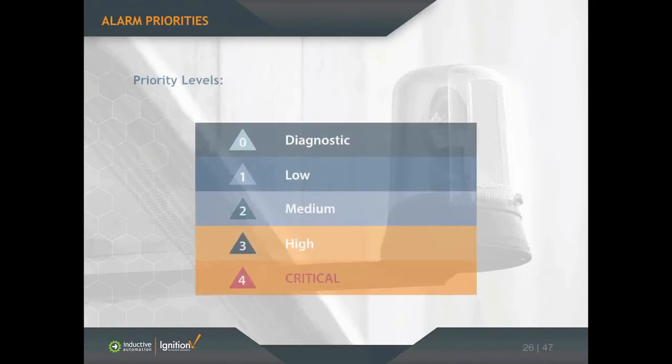After you configure any alarm, you also need to give it that priority. There are five priority levels in Ignition: zero is diagnostic, one is low, two is medium, three is high, and four is critical.